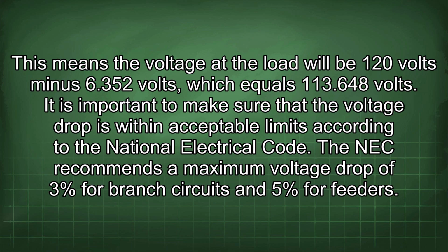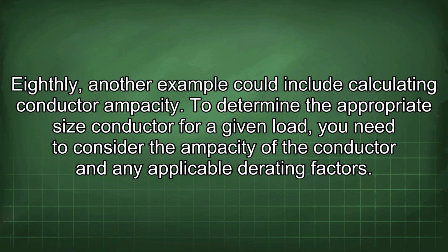It is important to make sure that the voltage drop is within acceptable limits according to the National Electrical Code. The NEC recommends a maximum voltage drop of 3% for branch circuits and 5% for feeders. Eighthly, another example could include calculating conductor ampacity.